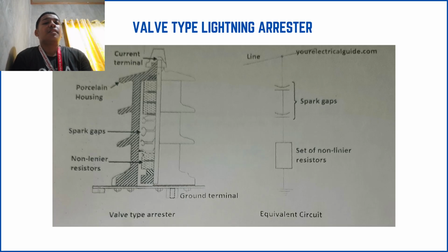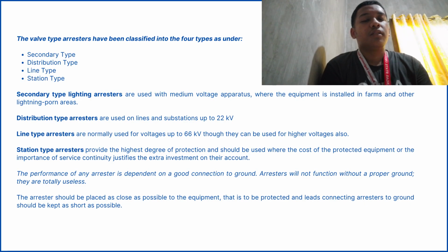On the right side, we have the equivalent circuit. It represents the combination of spark gaps and nonlinear resistors connected between the line and the ground. This model helps us understand how an arrestor conducts only during overvoltage condition. Next slide. We can see how the valve type arrestors are classified. They are divided into four main types based on their application and voltage level.